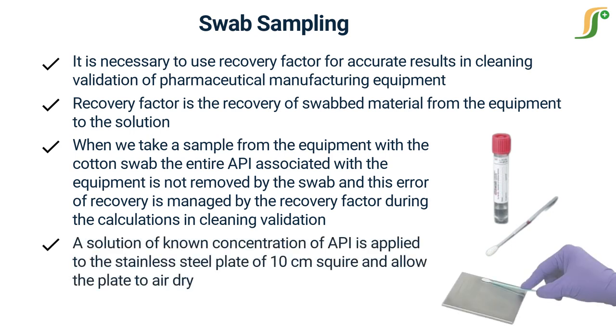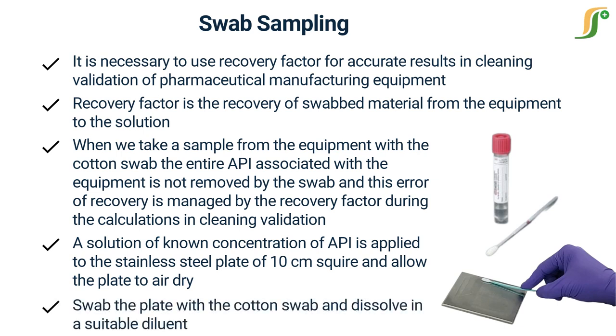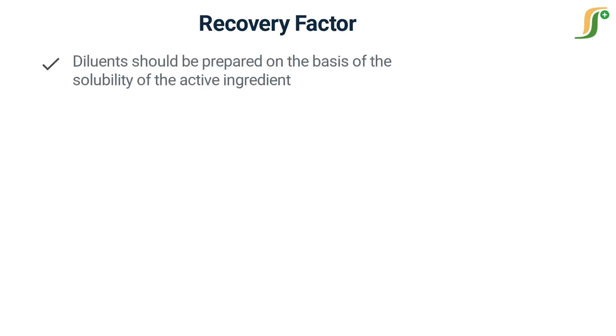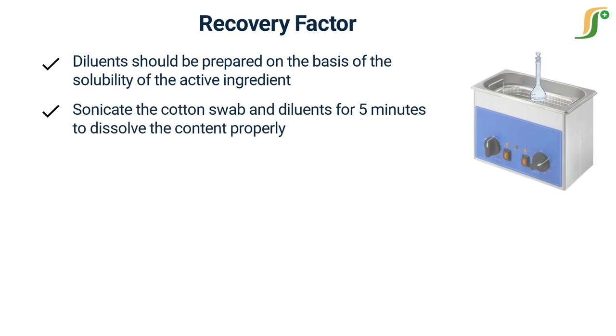A solution of known concentration of API is applied to the stainless steel plate of 10 centimeters square and the plate is allowed to air dry. Swab the plate with the cotton swab and dissolve in a suitable diluent. The diluent should be prepared on the basis of the solubility of the active ingredient. Sonicate the cotton swab and diluent for 5 minutes to dissolve the content properly.